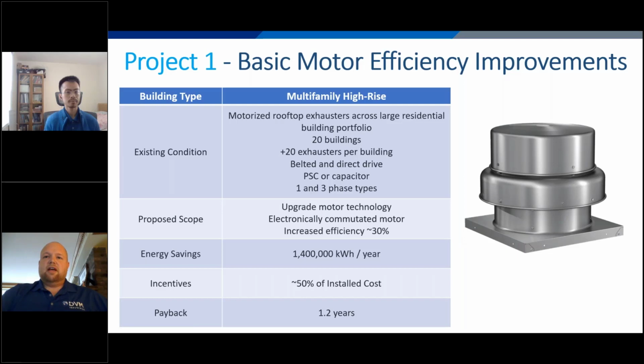So what we proposed to the client was to upgrade specifically the motor inside these units to a higher efficient design. It's known as ECM, electronically commutated motors. Across the 20 buildings, there were 20 exhausters per building, so over 400 of these across the whole portfolio. And this wound up saving the client 1.4 million kWh a year. So it was a pretty big reduction in input energy.